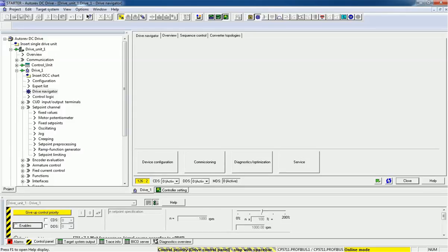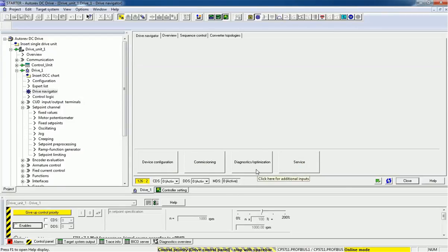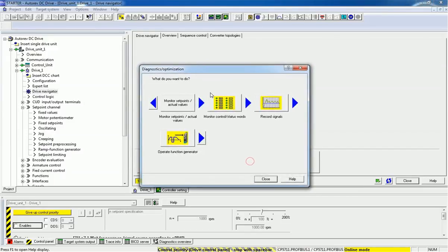In our previous video we saw how to configure a DC drive using Starter software. Now in this video we will see how to make optimization. I have already configured a Siemens SINAMICS series DC drive 6RA80. Now I will go to the Drive Navigator and from there we get options: configuration, commissioning, optimization, and service. I will go to optimization first.